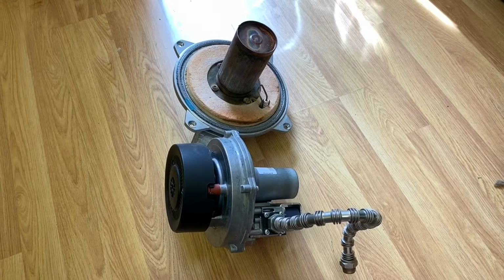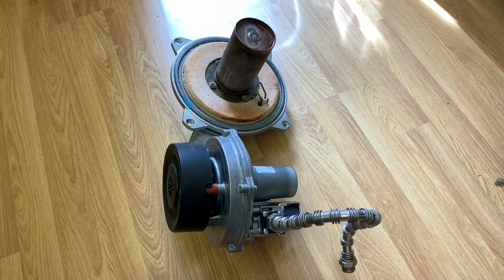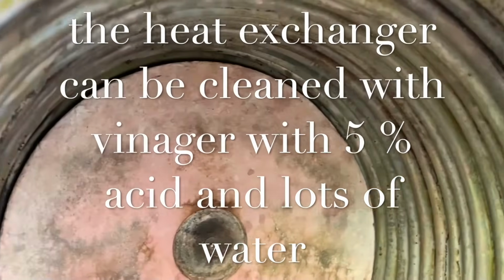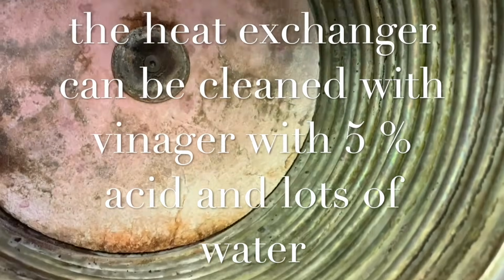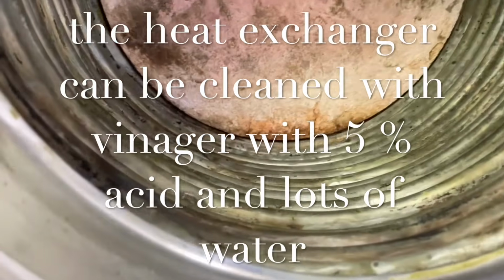So now we've got that out, let's have a look at the bottom of the boiler more closely and look at this water set. We can also see inside this heat exchanger now. So these are what we call a 2-pass heat exchanger. So there's 2 lots of flow and returns in here in a coil, and there's 10mm stainless steel pipes.